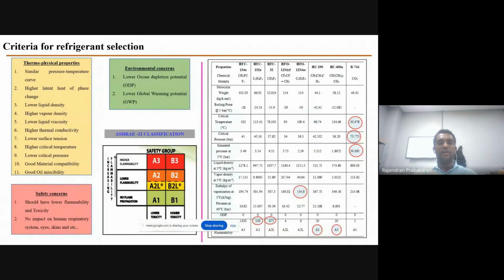So next, criteria for refrigerant selection. Usually the refrigerant will be selected based on 3 aspects: thermophysical properties, environmental concerns, and safety concerns. The refrigerant should have good thermophysical properties, including high latent heat of phase change, low density, high vapor density, high thermal conductivity, low surface tension, etc. On the other hand, it should have no ODP and a lower GWP. So these two are for the system performance and environmental consequences. And the third one is safety concern.